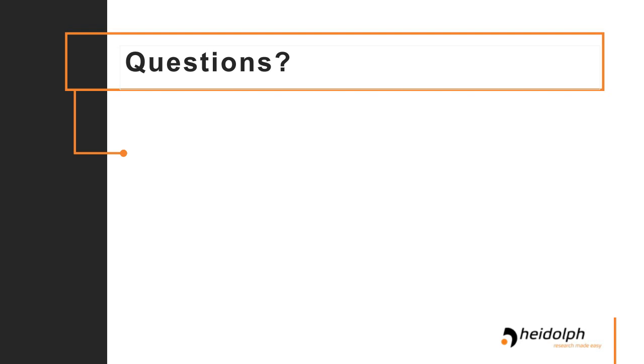That's a good question, I can take that. It depends highly on the application you run, and also the frequency of use for the rotary evaporator. Sometimes rotary evaporators are used only 1 or 2 hours a day, but sometimes they run 8 hours or more, which has a huge influence on the lifespan. But all in all, for our products we promise 10 years of lifespan. It depends on the parts built inside the evaporator, and of course you're always in a very aggressive environment. Regarding wearing parts, for the most quality systems, you only have to replace the vacuum seal. This is an essential part regarding service and your cost of ownership over a long lifetime.